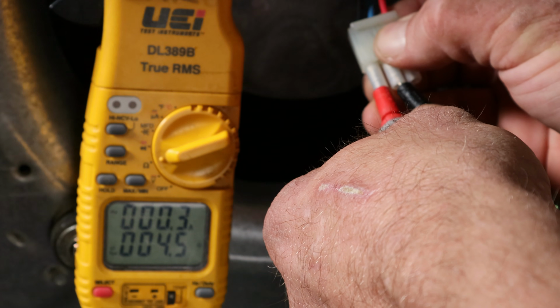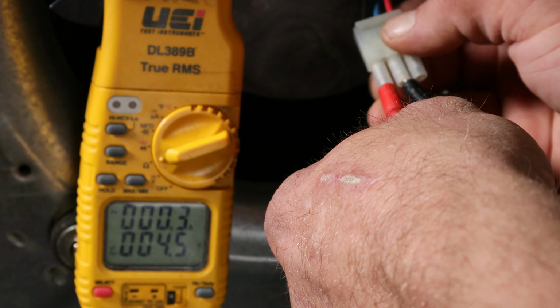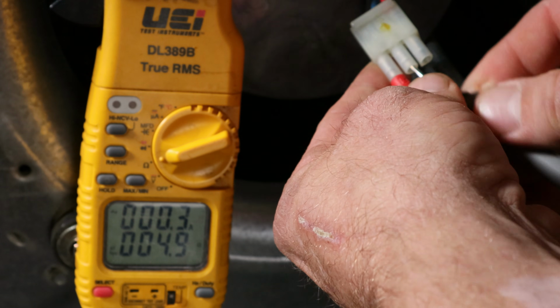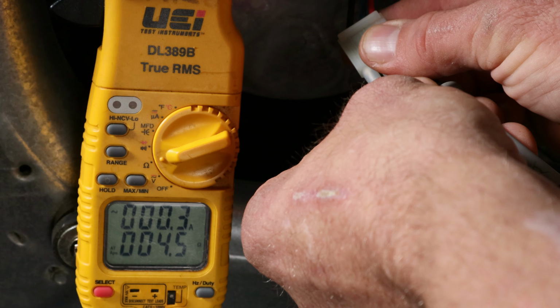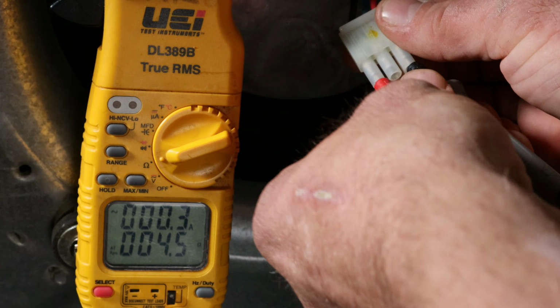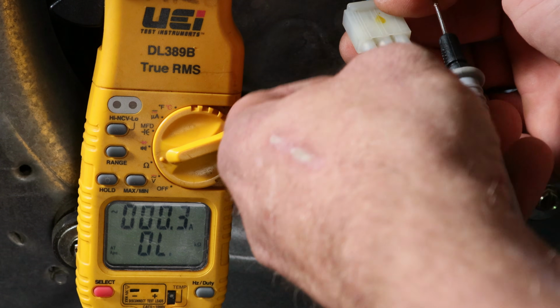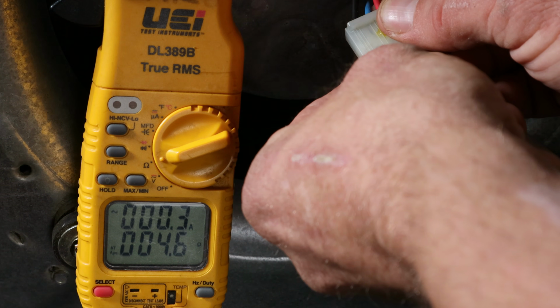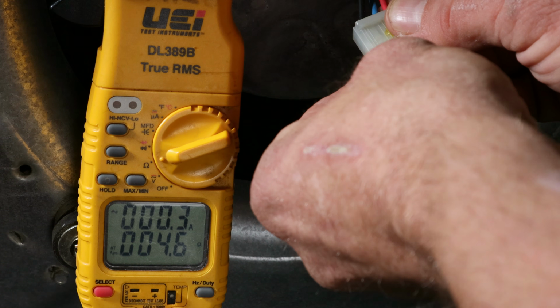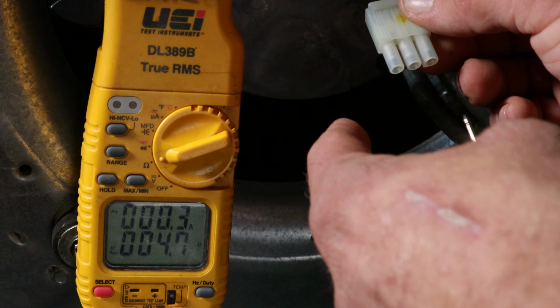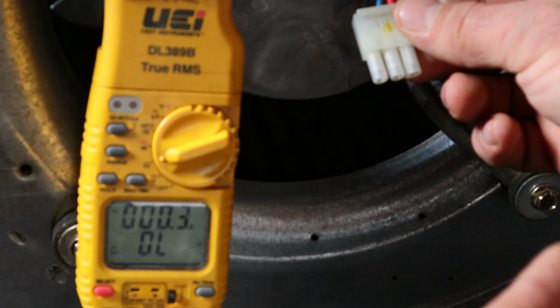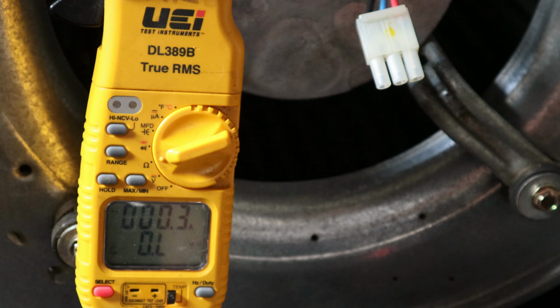You see I'm reading about 4.7 ohms there. I am then going to go from black to red, and I'm reading about 4.5 ohms there. I am then going to go from blue to red. You see I'm reading about 4.6. So all 3 of these readings should be close to the same, just like a regular 3-phase motor, and they should all be within about 10% of one another.